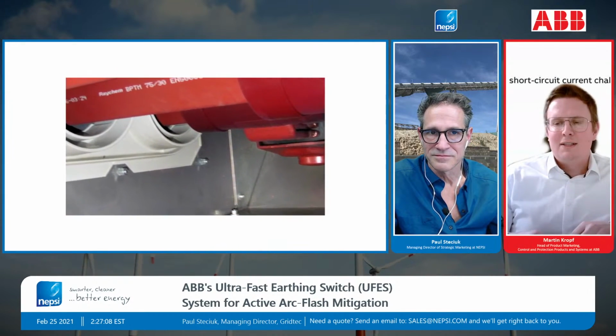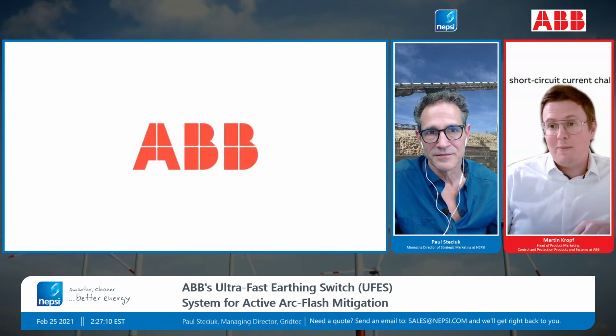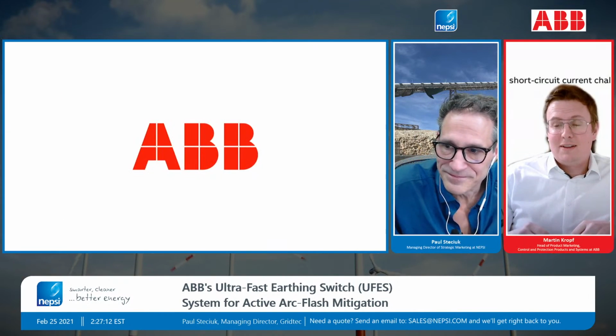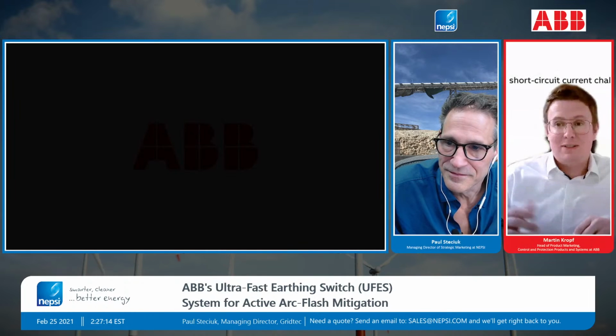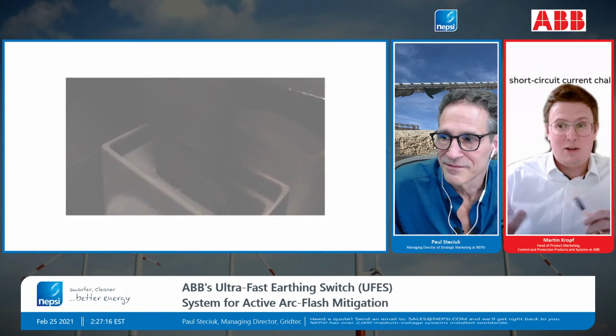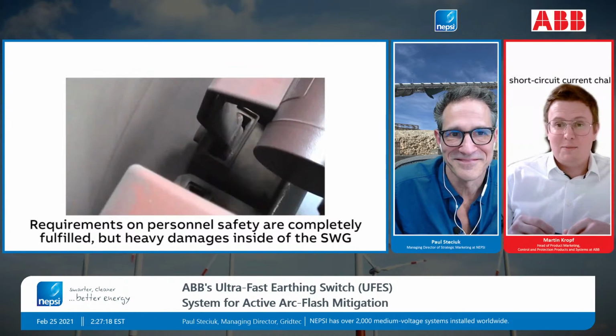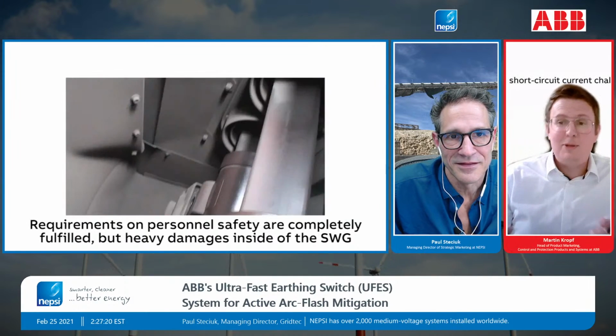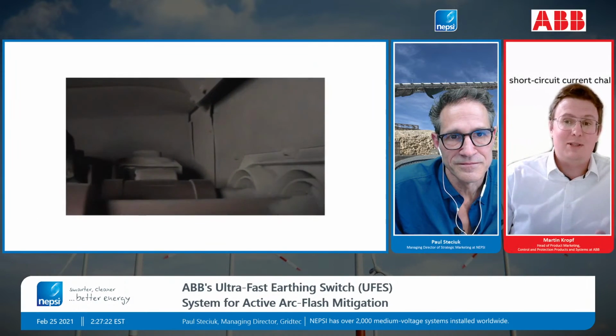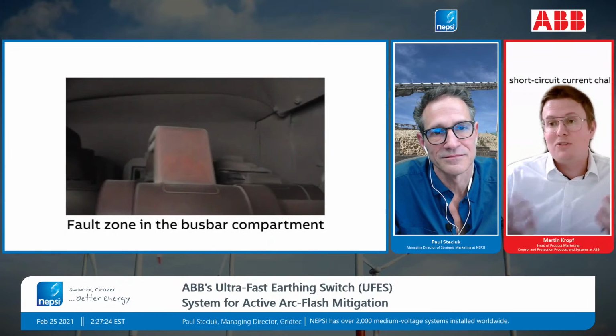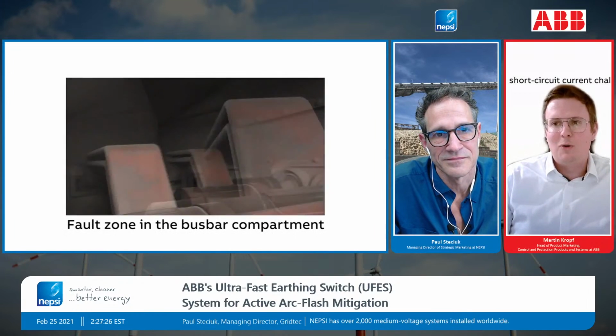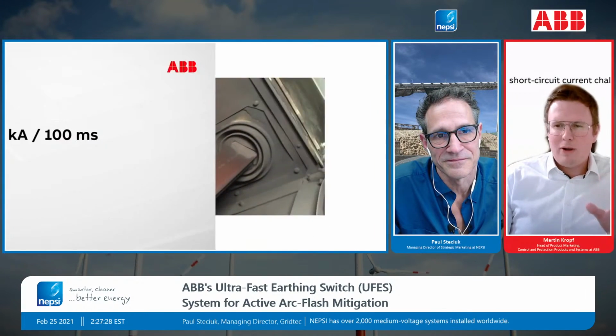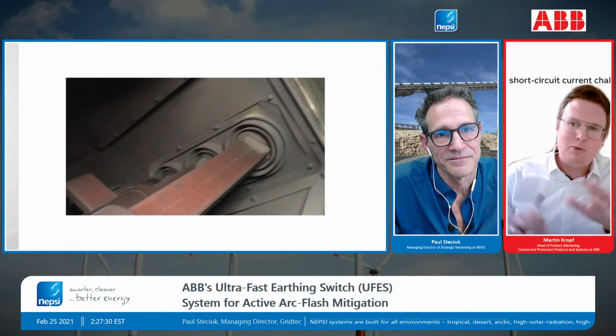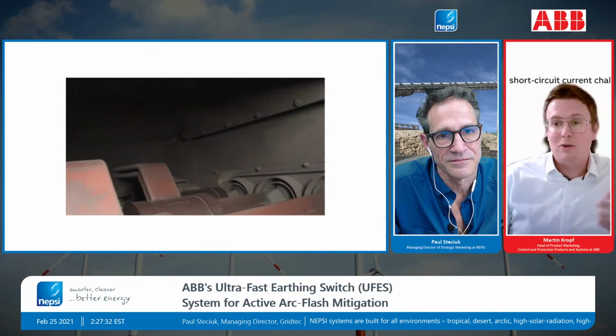We actually had an application once, a real tripping of UFES, and the customer came to us and said, "Look, it has wrongly tripped," because there were no traces. Then we looked at the records and saw it had perfectly worked, but it was just so fast that there were no traces. So it's a benefit to have point light sensors if you have a very distributed system, because then you know where to look.